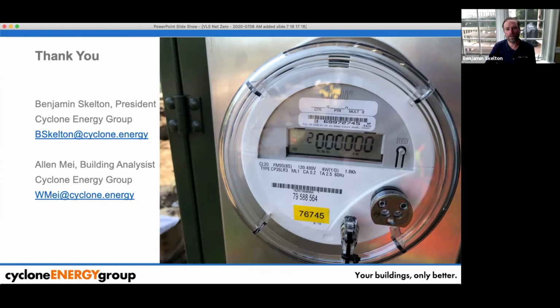And so this went on for a month, and we got the data, and we were doing an evaluation to calibrate it to our modeling system. And I actually have a cool graphic I left out of this, but it shows all of a sudden you see everything's following our model just perfectly, and then all of a sudden the lighting controls just go straight, a straight line. We couldn't figure out why this was going on, so we went out to the building and evaluated it, and we saw that all the lights were running at 100%. It was a user error, but it was a maintenance issue that people hadn't realized was happening. And so once we trained the operator and they realized what the proper code was to set the alarm into inactive, we were able to get that building back on track.